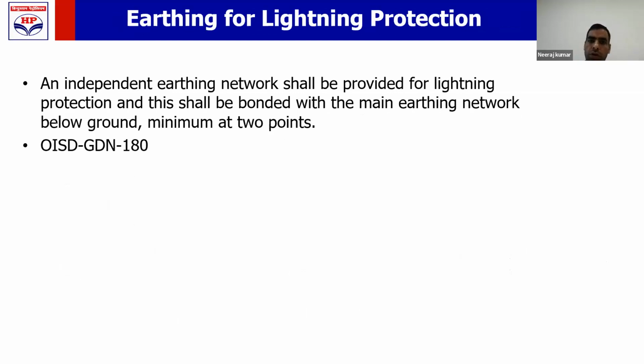A special requirement of lightning protection requires discussion here because lightning can also be an ignition source. So for lightning protection, OISD-GDN 180 is to be referred. In addition to the requirement of GDN 180, the requirement given by this standard is that the earthing network made for lightning protection shall not be the same as the one made for your plant. You will have one earthing network made for your plant and one more earthing network made for your lightning protection. And then you should connect these two networks at two different places. It is not okay to use the network of your existing plant for the lightning protection network also.